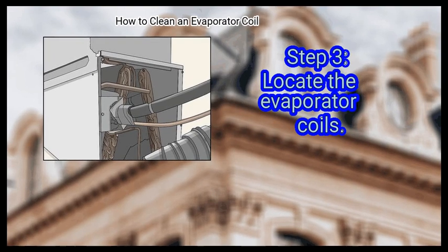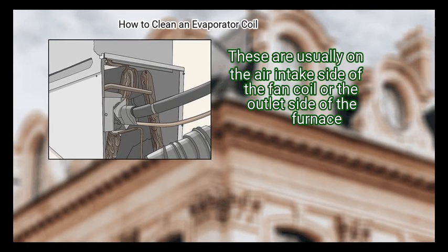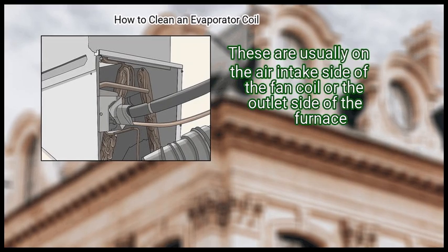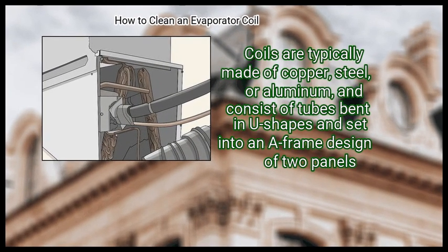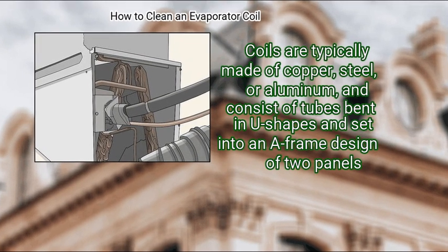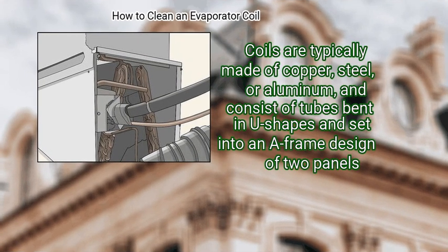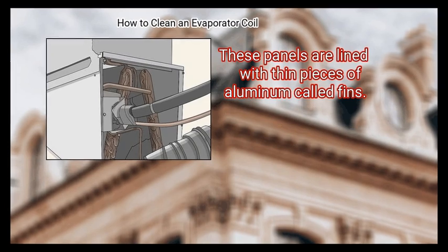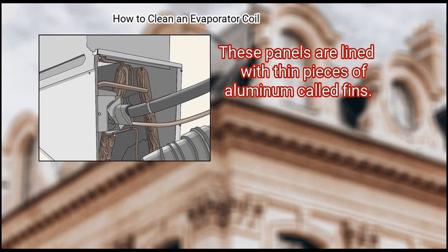Finally, locate the evaporator coils. These are usually on the air intake side of the fan coil or the outlet side of the furnace. Coils are typically made of copper, steel, or aluminum, and consist of tubes bent in U shapes and set into an A-frame design of 2 panels. These panels are lined with thin pieces of aluminum called fins.